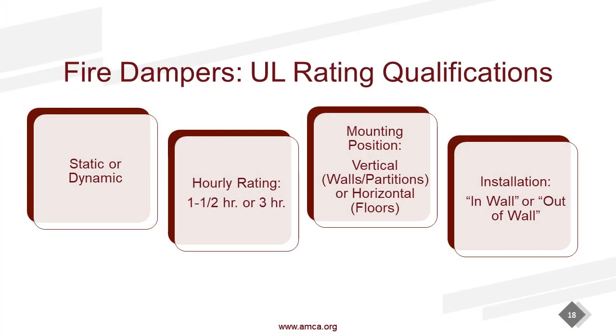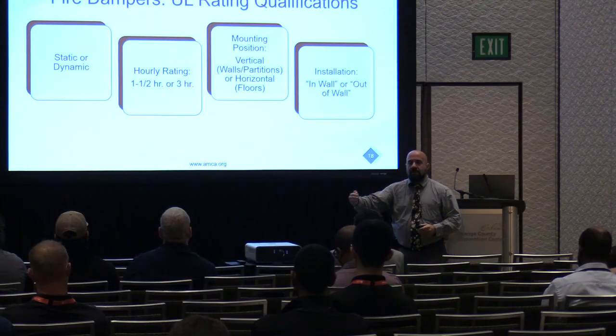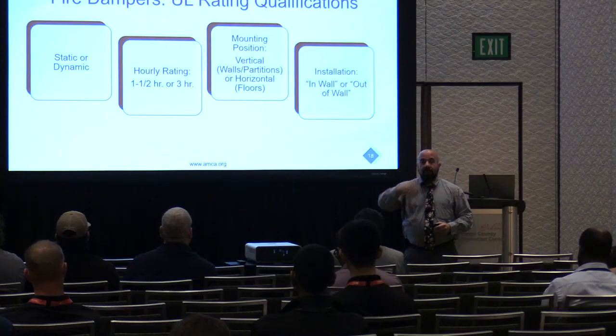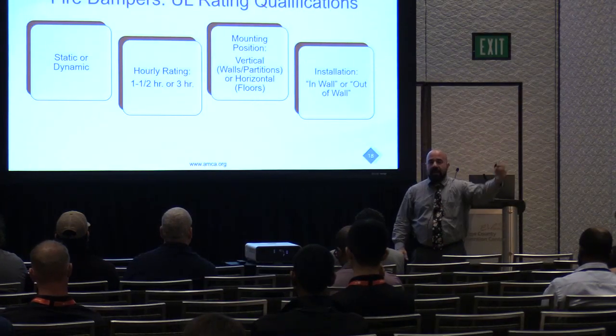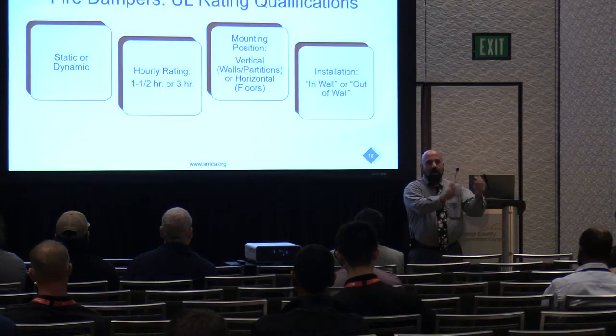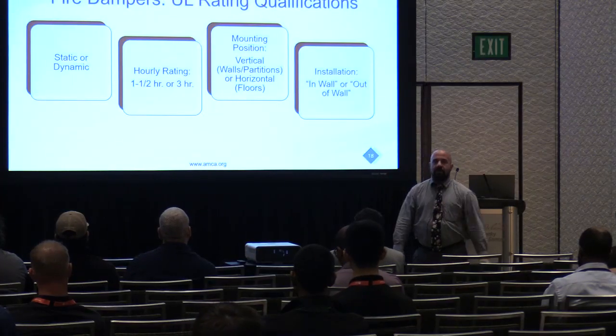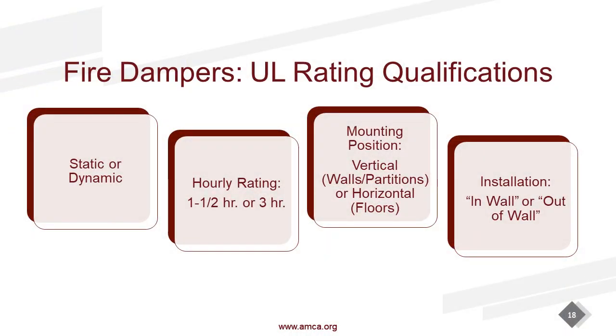When we go through our 555 series of tests, we go through a litany of tests to earn our certification, right? We replicate as much real-world conditions as we can in a laboratory, and we do that uniformly across the industry for every damper that's certified. So my specifiers can look at manufacturer A and manufacturer B and be assured they were all tested to the same requirements. There's no difference, there's no interpretation, and it's all unanimous, homogeneous. When we go through that testing, we earn our certification, whatever's on that UL label. So I call this my damper Carfax.